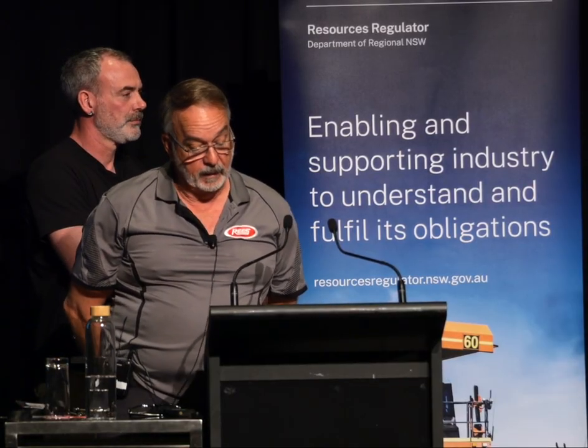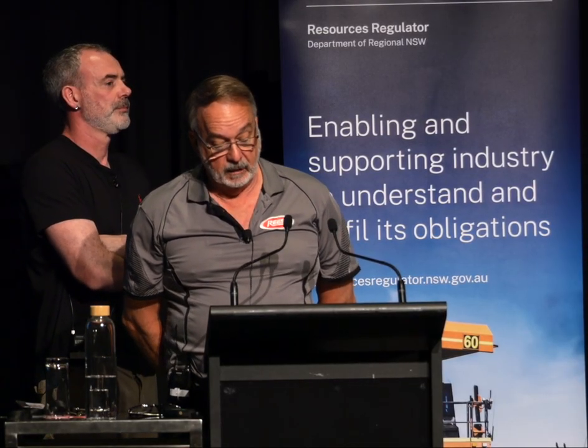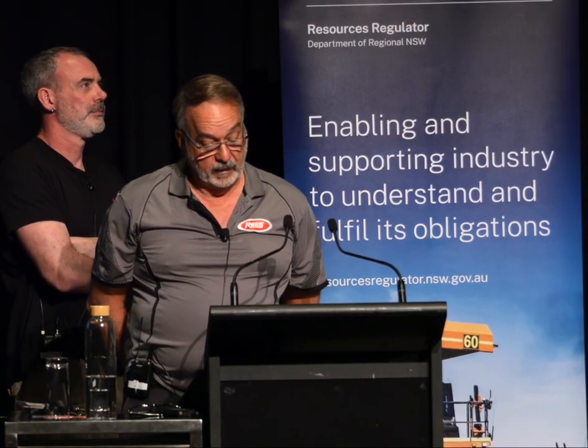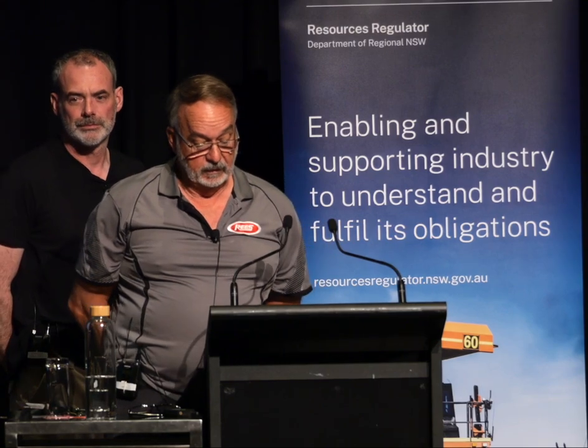Number two was to access the unit. Number three would be to ground all the equipment. Step number four would be to take oil samples. And then number five would be to drain the oil. We then replace the oil and the immersed gaskets and allow at least half an hour for draining. Then we would flush with hot FR3, around 5% of the fluid volume. Allow another half an hour for drip after draining.